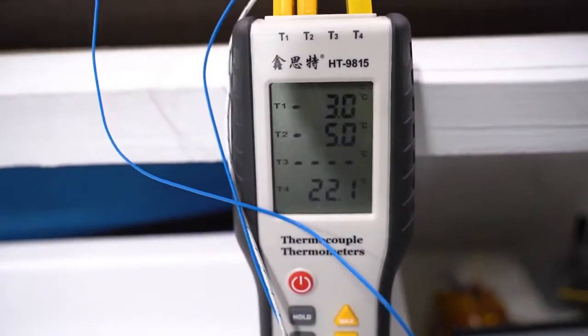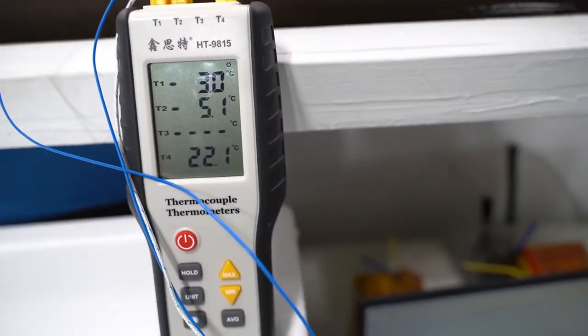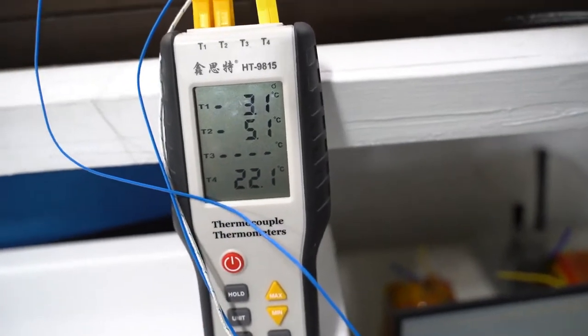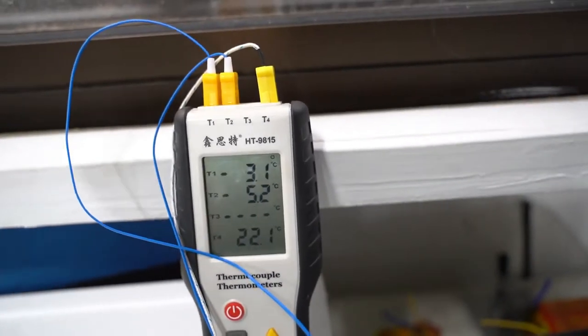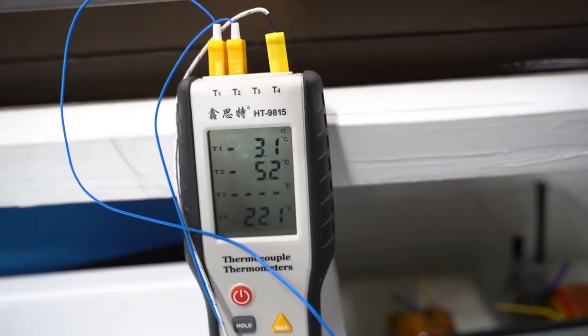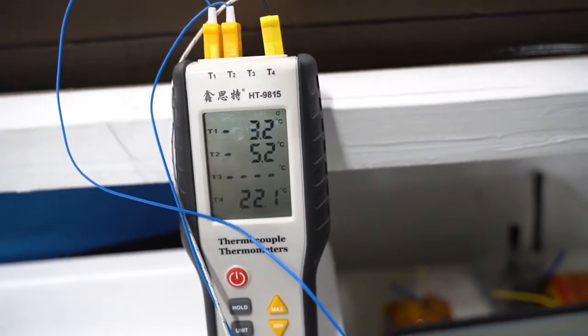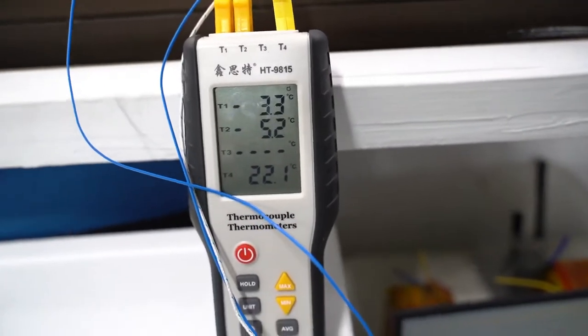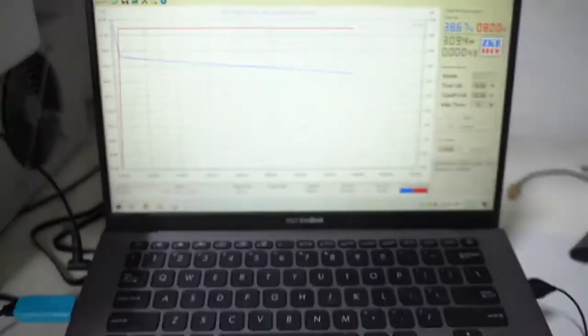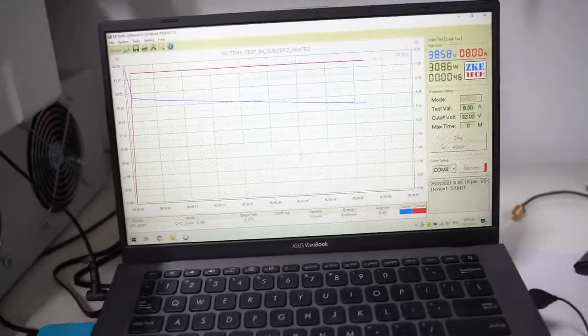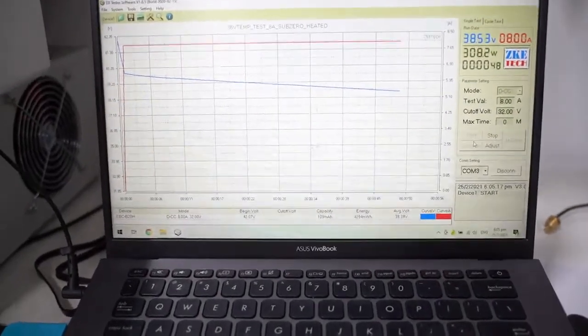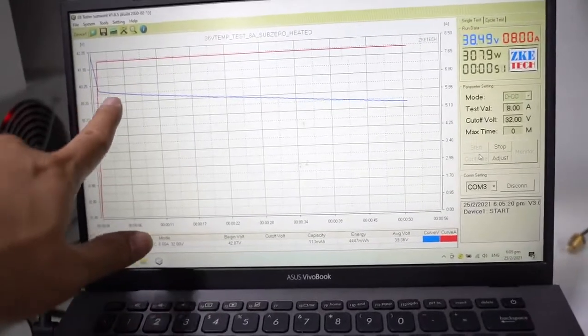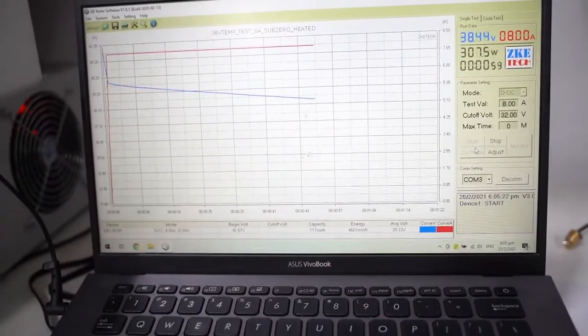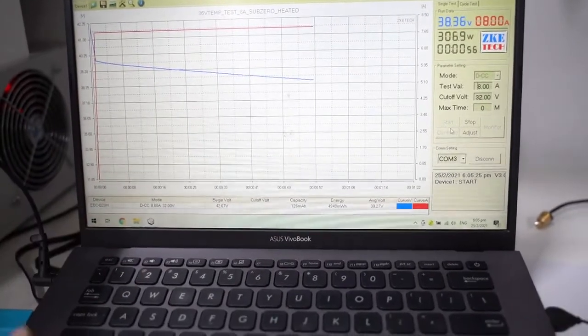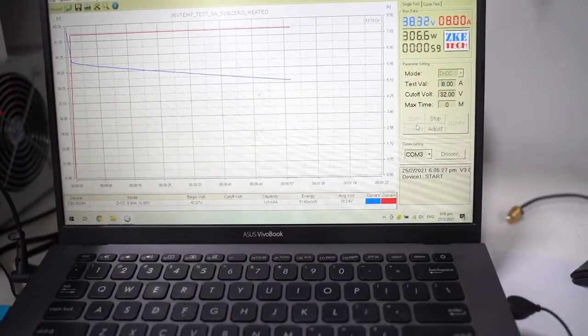Let's look at the temperature. The temperature is at 22, which is not bad. That's ideal because the heating element's on. 22 is actually a good temperature to run at. Of course, in the ideal operating environment, we want the battery temperature to be around 25 to 40 degrees. So this is fairly close, and this is really good. That means our material is actually retaining the heat pretty well. You can see the discharge curve is relatively linear, which means that the battery cells are stable and behaving predictably.